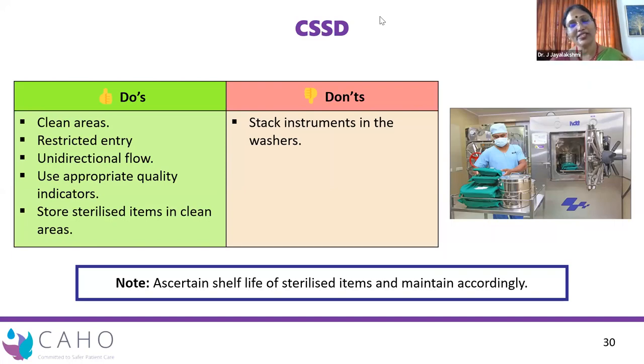So at least 20 to 25 centimeters above the floor and at least 5 centimeters away from the wall. This is a basic simple requirement for your instruments, which are stored and packed and after sterilization, ready for issue.